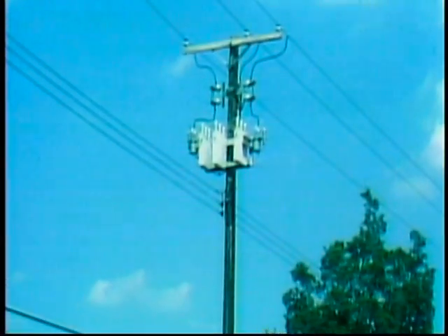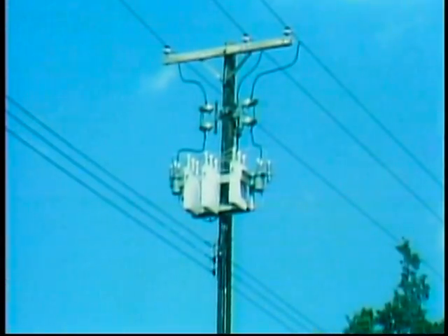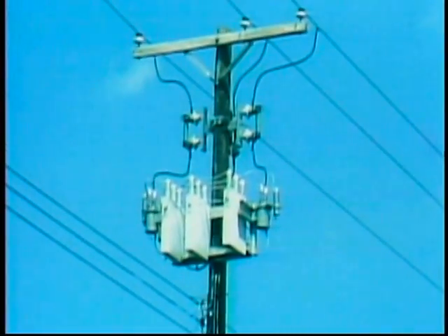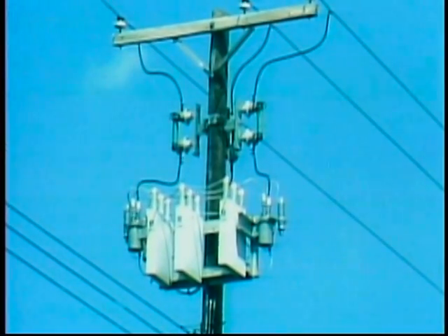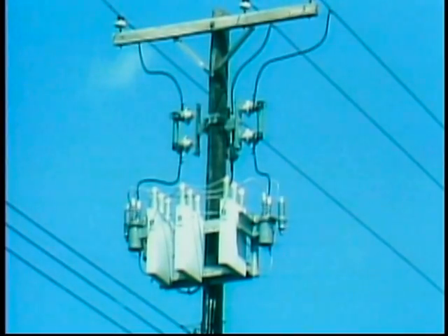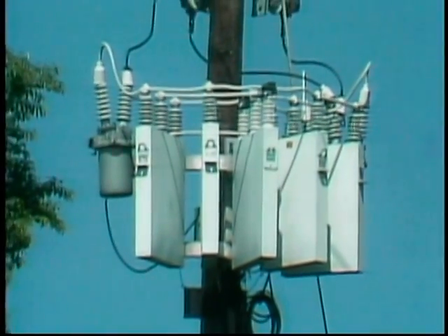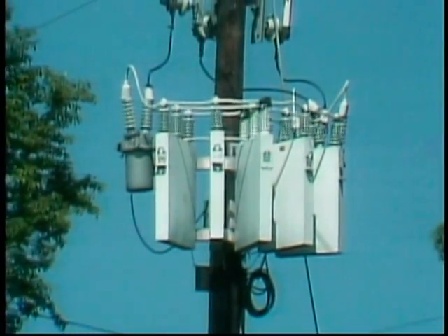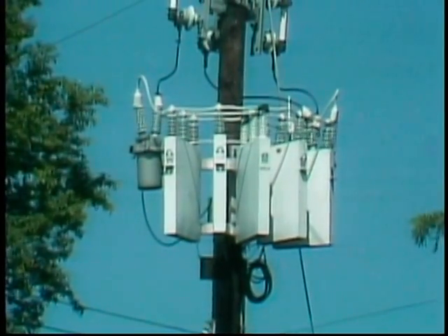The function of a capacitor is to improve power factor. This is done either by switching capacitors into a circuit to add capacitance to the lines, or by switching capacitors out of a circuit to remove capacitance from the lines. Distribution transformers, voltage regulators, and capacitors all keep the distribution system working efficiently and at the proper voltages. A variety of other pole-top equipment works to protect the distribution system.